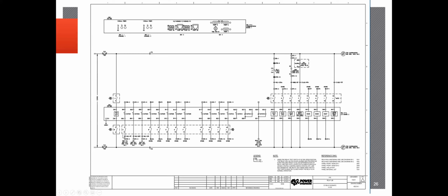The reason you do your trips first and not anything else is because this is your primary form of completely messing up and operating the breaker inadvertently. If you were to pull all your voltages first from the relay, well, the relay sees no voltage. There's got to be a fault on the line because it's still reading current going in and out. So let me open up the breaker. Well, you don't want to do that yet. You've got to properly isolate it. So you start with your trips.